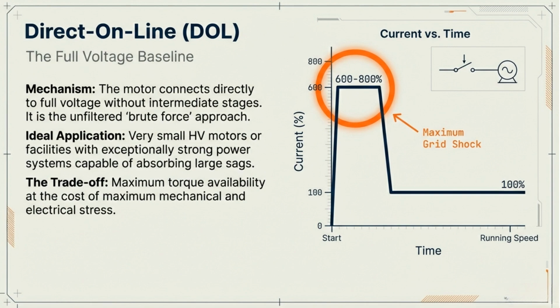Direct-on-line, or DOL, is the full voltage baseline. The motor connects directly to full voltage, resulting in maximum torque at the cost of maximum electrical and mechanical stress. This approach is ideal for very small HV motors or facilities with strong power systems.